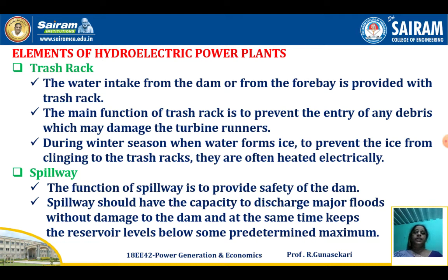The water intake from the dam or from the forebay is provided with the trash rack. The main function of the trash rack is to prevent the entry of any debris which may damage the turbine runners. During winter season, when water forms ice, to prevent the ice from clinging to the trash racks, they are often heated electrically. The next one is the spillway.